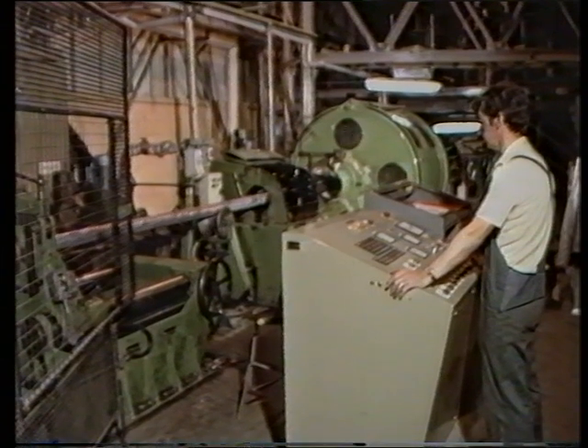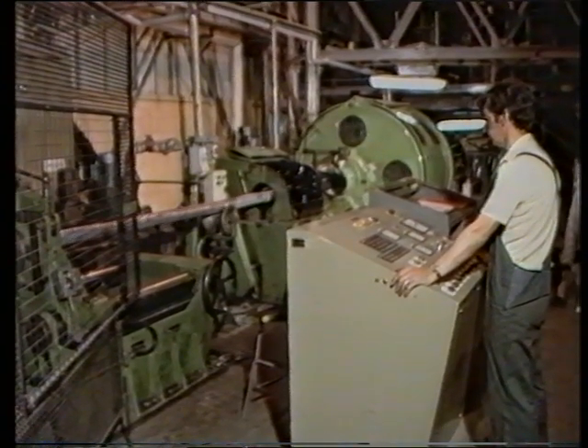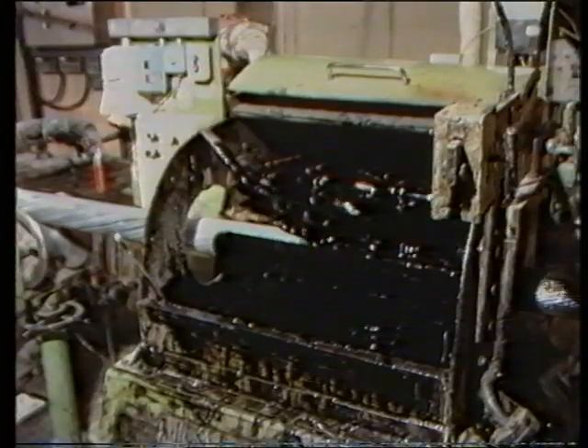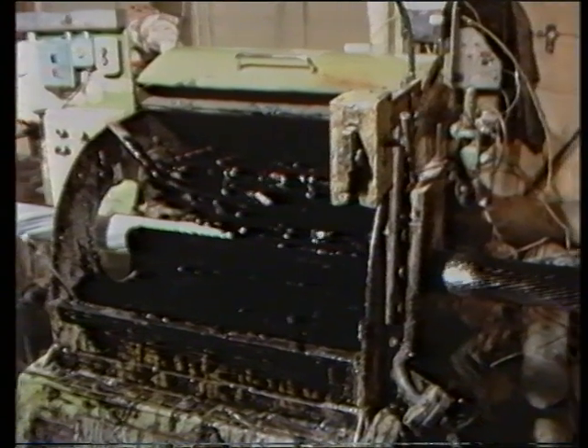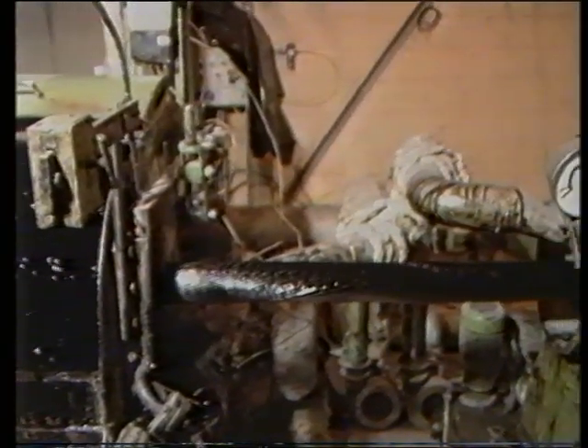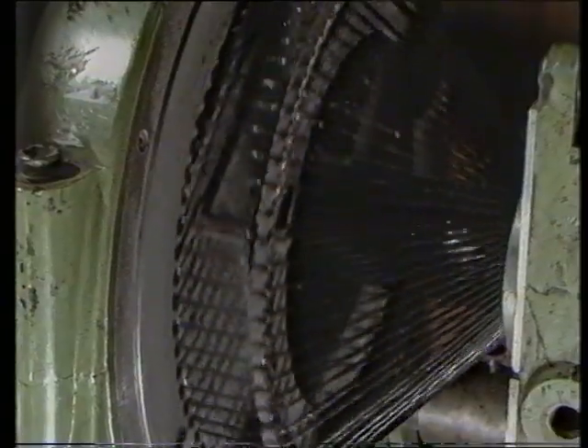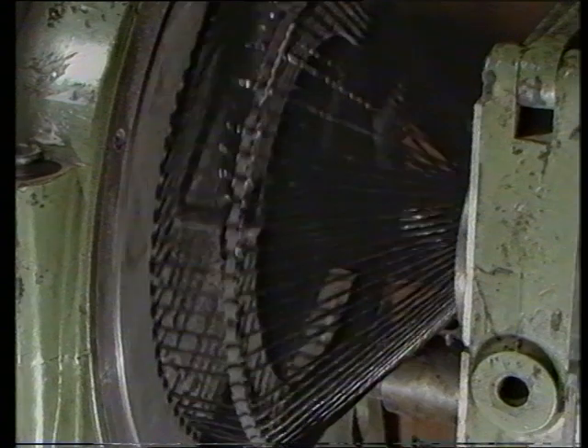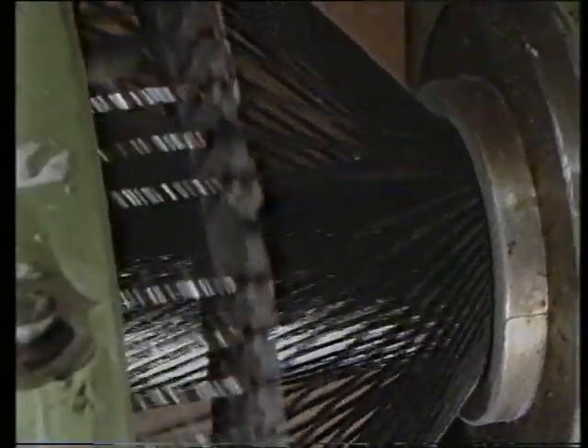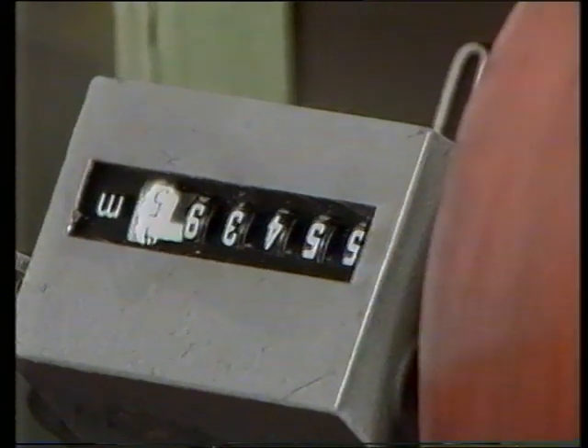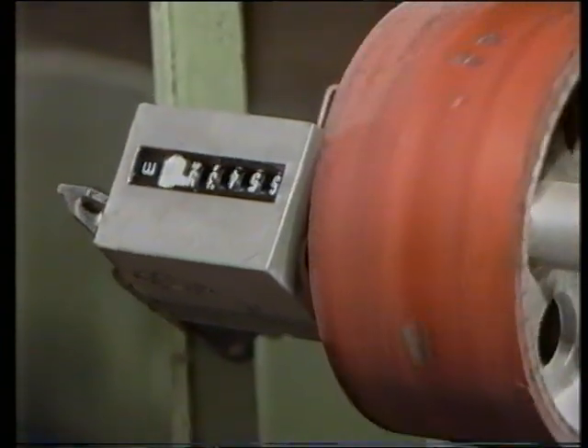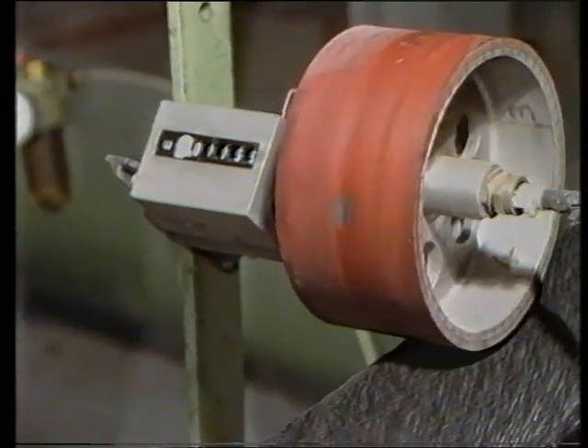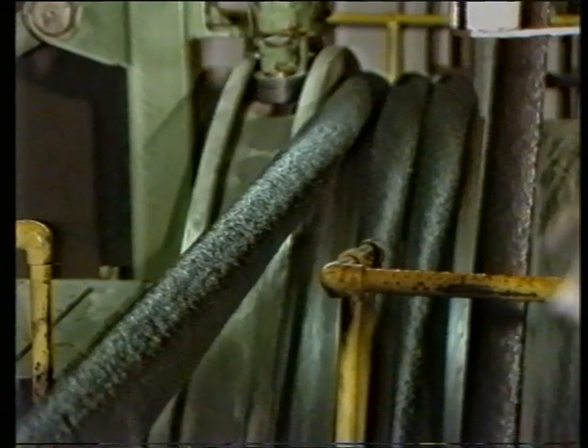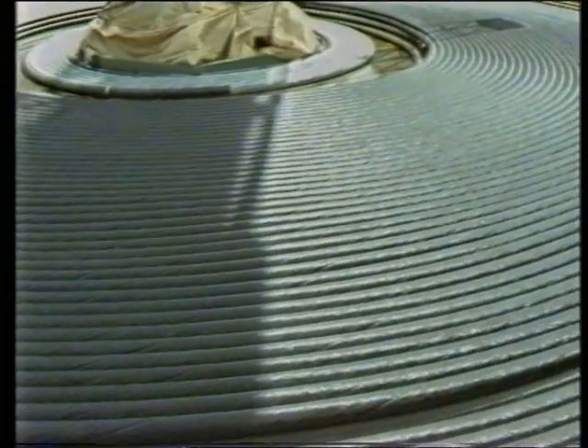A final check on the shape of the cable, and then, as a further protection against possible corrosion, the armour is covered with bitumen. The last layer of all is the serving, polypropylene string which is wound on top of the bitumen. Almost 60 kilometres of cable are made by Pirelli, and they weigh over 1,200 tons. It's a triumph of professionalism and skill, owing much to Pirelli's long experience in this very specialised field.